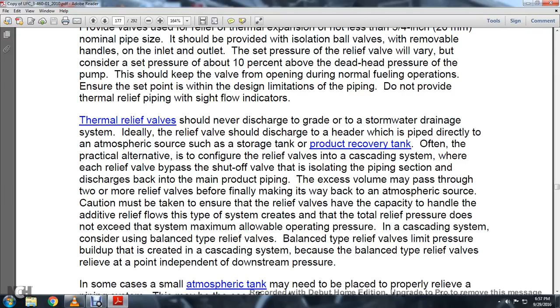Caution must be taken to ensure the relief valves have the capacity to handle the additive relief flow the system creates, and the critical relief pressure does not exceed the system maximum allowable operating pressure. In a cascading system, consider the use and type of the relief valve, the balanced type. Relief valves limit pressure buildup created with the cascading system pressure. The balanced type of relief valve relieves at a point independent of the downstream pressure.